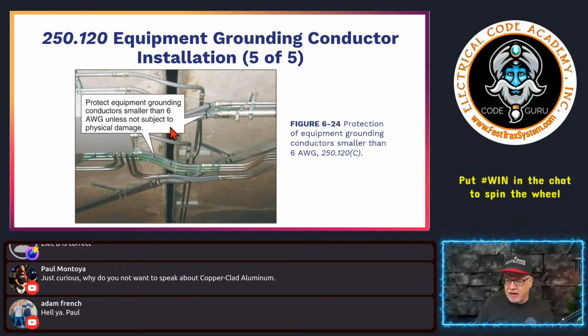And this is an example of where they're allowed to run this. They're running this equipment grounding conductor outside of it. All right. But it's got to be protected unless somebody determines that it's not subject to physical damage. Now, I would argue, I don't know that these are actually equipment grounding conductors, but it's just a good picture, just showing some green being run out on its own. But if somebody determines that it's subject to physical damage, then it has to be protected, okay?